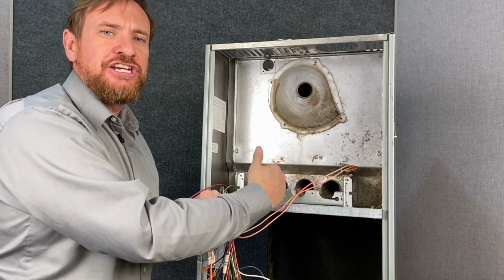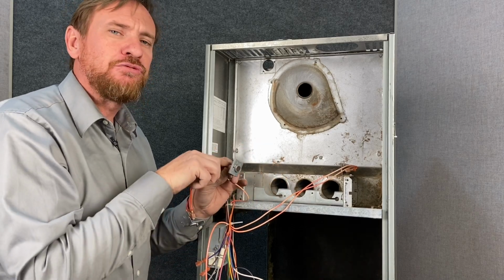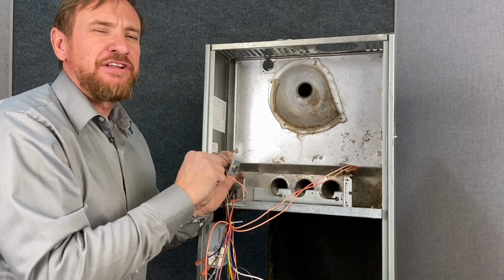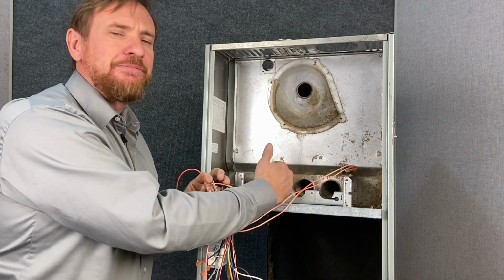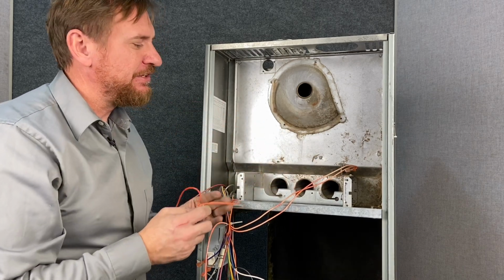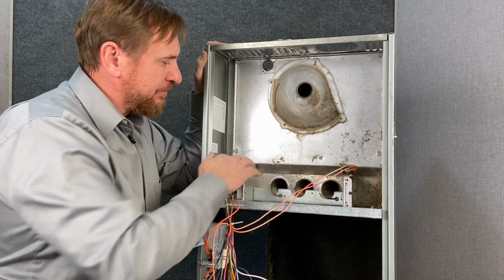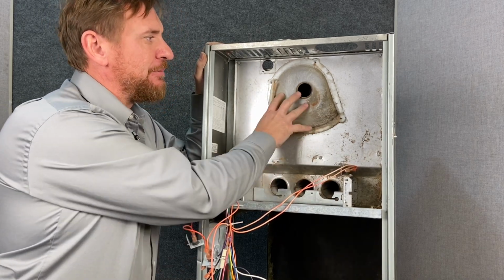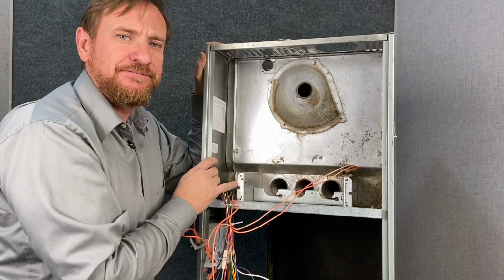We want to check that heat exchanger. We want to check everything about it. We do not just want to reset that. I've never seen one of these limits trip without having some kind of an issue. Find that issue and solve that issue. So what we're going to do next, we're going to take the last of these components off, and then we're going to pull this heat exchanger out of this unit.